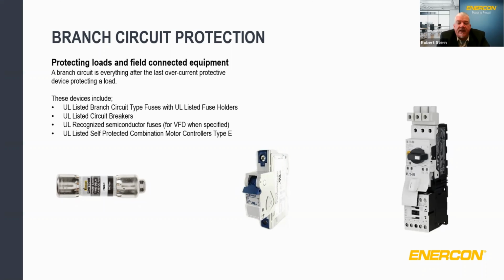Amperage for protective devices is calculated based on the FLA, or full load amperage, of the intended devices that are within and connected to the industrial control panel and intended to be powered from the circuit. It's required to know the endpoint specific loads that will eventually be connected to the field terminals of the panel to properly size the components needed for the branch circuit protection, because applications like lighting, heating, and motor control loads require additional margin to safely operate due to their ability to draw large amounts of power.